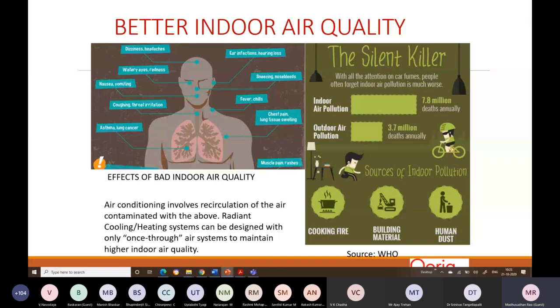Recirculation of air can be avoided by using radiant cooling, though ventilation is still needed—but fresh air is only about 10 to 15, maybe up to 20%, of the overall energy load. We've designed projects with 100% fresh air, where air from outside enters the building once and goes out without recirculating, providing a very healthy environment.